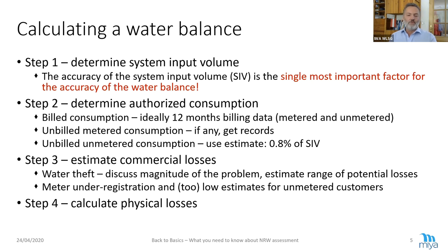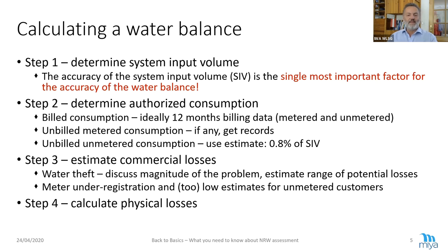Then we need to determine the authorized consumption. We have billed consumption, which is ideally from 12 months of billing data. If you do a water balance for one month, it's a rather difficult job, because you can read the system input meter on the first and last day of the month, but all the customers' meters are read over the year. So you need to analyze the billing data in great detail. If you do it for one year, you don't have a problem with the billing data — it's rather simple.